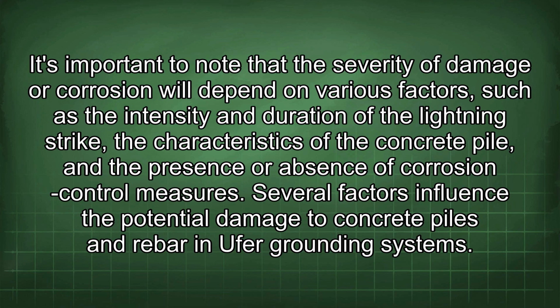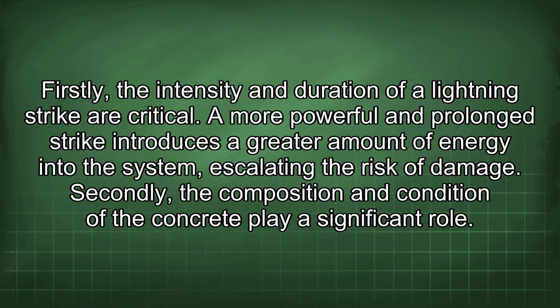It's important to note that the severity of damage or corrosion will depend on various factors, such as the intensity and duration of the lightning strike, the characteristics of the concrete pile, and the presence or absence of corrosion control measures. Several factors influence the potential damage to concrete piles and rebar in Ufer grounding systems. Firstly, the intensity and duration of a lightning strike are critical. A more powerful and prolonged strike introduces a greater amount of energy into the system, escalating the risk of damage.